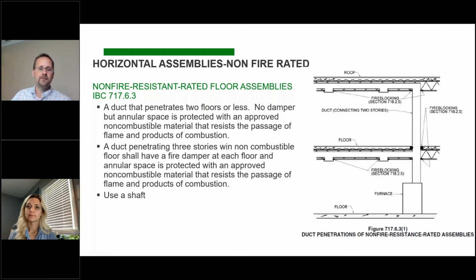So the way the section talks is if you have a duct that goes between 2 floors or less, if the floors are not fire rated, but the floors are made of non-combustible materials, you can get away with no shaft and no fire dampers at the floor, assuming you do good fire caulking and seal around the openings. And this diagram here is from the code commentary that describes what they're discussing with connecting 2 floors and the fire caulking. Now, if you go between 3 floors, so a little bit taller building, you still don't have to have a shaft if you have non-rated floors, but you need to make sure that you have, again, a fire damper at each floor in order to avoid that shaft.